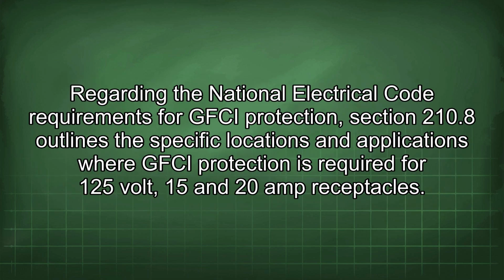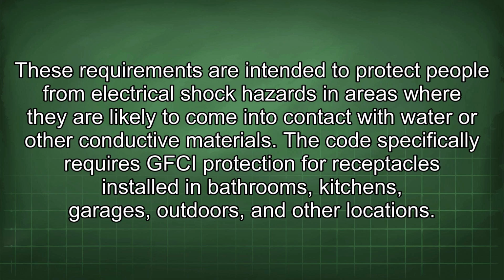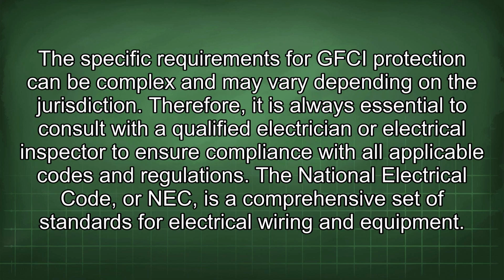Regarding the National Electrical Code requirements for GFCI protection, Section 210.8 outlines the specific locations and applications where GFCI protection is required for 125-volt, 15 and 20 amp receptacles. These requirements are intended to protect people from electrical shock hazards in areas where they are likely to come into contact with water or other conductive materials. The code specifically requires GFCI protection for receptacles installed in bathrooms, kitchens, garages, outdoors, and other locations. The specific requirements for GFCI protection can be complex and may vary depending on the jurisdiction.